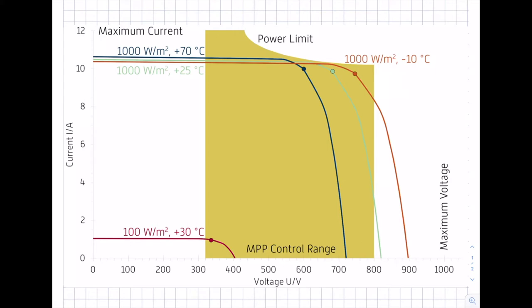The inverter has several technical parameters which limit its capacity. On the one hand, there is a maximum voltage which the inverter can handle. In this case, the inverter has a maximum voltage of 1000 volts, which is the typical value for a modern inverter. If the voltage increases above this value, you might damage the inverter. So we have to check that the number of modules connected in series does not result in a voltage exceeding this limit.